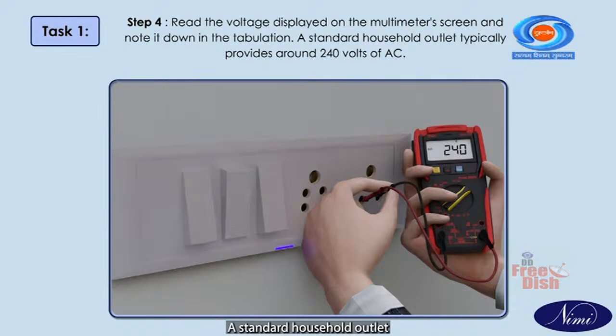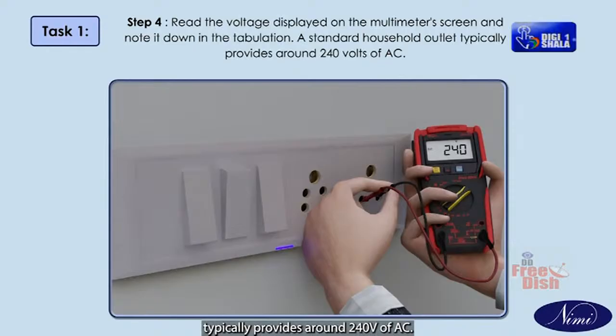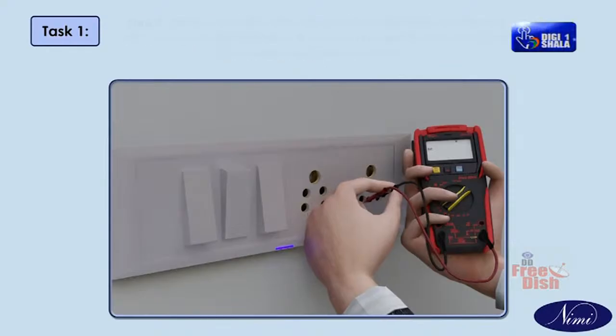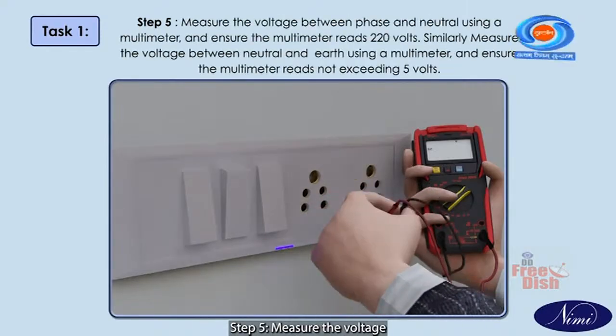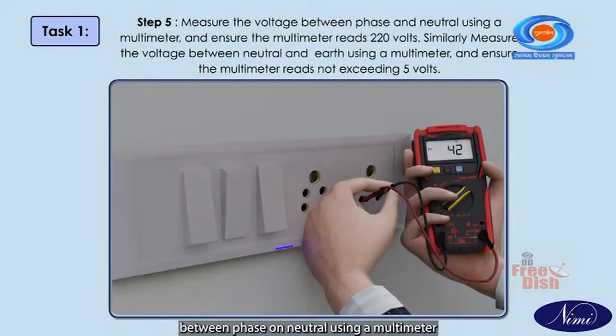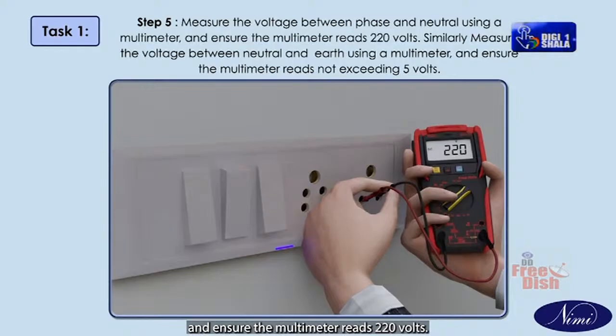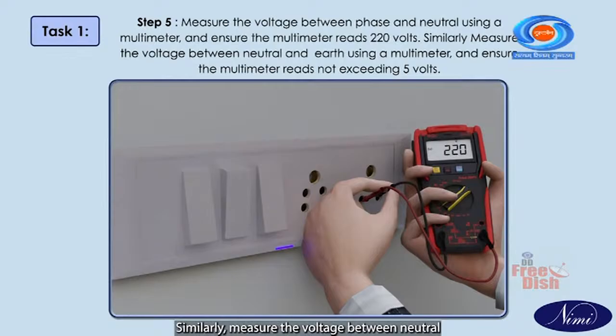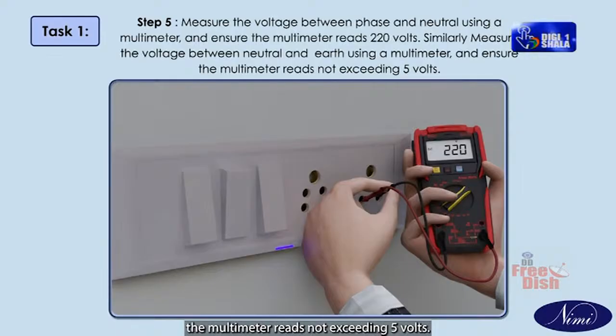A standard household outlet typically provides around 240 volts of AC. Step 5. Measure the voltage between phase and neutral using a multimeter and ensure the multimeter reads 220 volts. Similarly, measure the voltage between neutral and earth using a multimeter and ensure the multimeter reads not exceeding 5 volts.